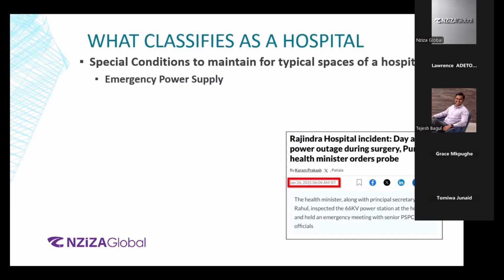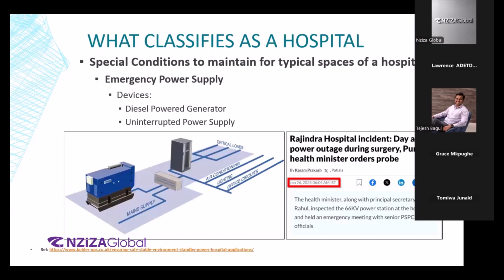Anywhere between 1 second to 10 seconds is required for a DG set to start. There is an automatic transfer switch that operates on an electromagnetic principle that takes anywhere between 1 to 10 seconds. And we are talking about a patient that is on the table, right? But in the case of UPS, it's split second. It can hold for the 10 seconds that the DG needs to start, but it is always good to have the surgery rooms, the operating theaters, on UPS as primary. So that is where devices such as the diesel generator and the uninterrupted power supply come into the picture.